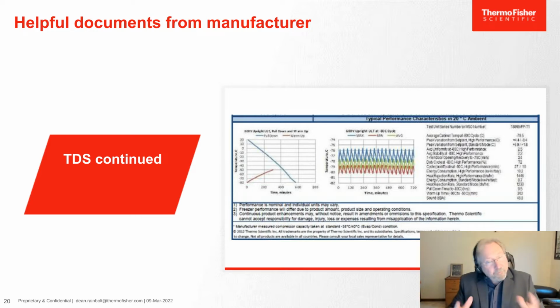Now also performance. Remember, we have to be plus or minus 10 of our desired temperature. Here at the bottom of the technical data sheet, it shows some performance testing done at the factory. Keep in mind, the factory will never know how you, or us as a customer, is going to test this freezer, so they have no idea. What the factory does is figure out where to put probes so they can ensure the freezer can operate within the specifications you want. But if you go to map this chamber with your own protocol, it's probably going to look a little different. The operation won't change, but the numbers won't be the same, though they'll be within your acceptance criteria.